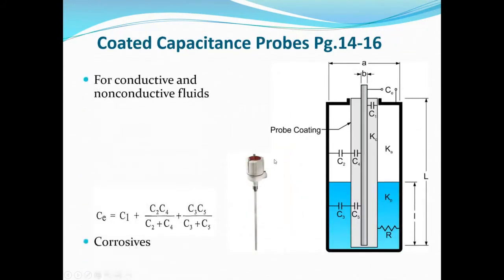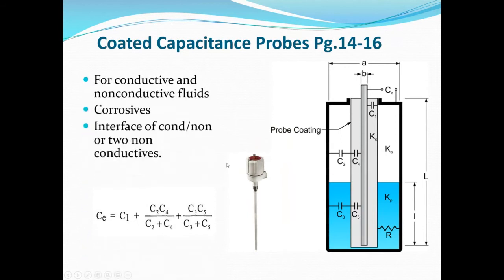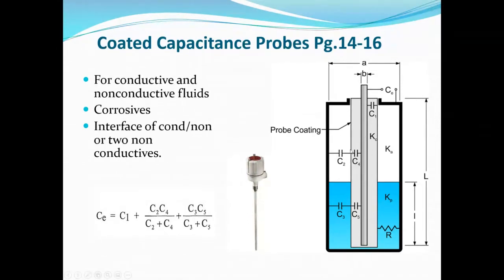Second style: the coated capacitance probe — good for both conductive and non-conductive fluids, good for corrosives, and can be used for interface measurement of conductive with non-conductive fluids. A common application in oil and gas: water is very conductive, oil is not, making a coated capacitance probe a good choice for a three-phase separator. Construction differs from the bare probe because capacitance is introduced by the coating — it looks like it has a Teflon-type coating on it.